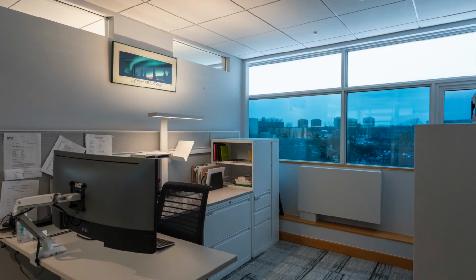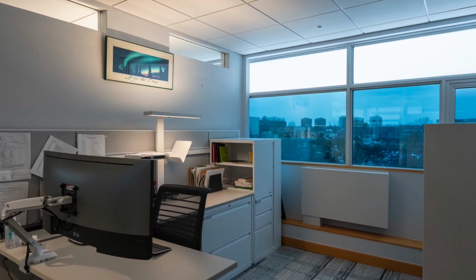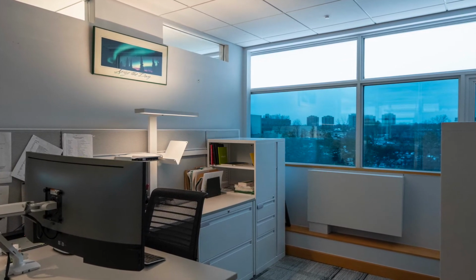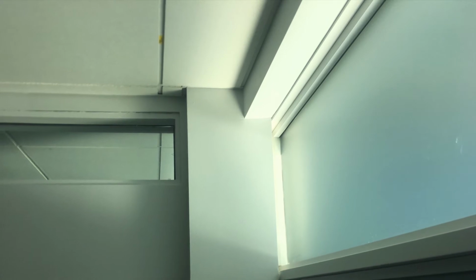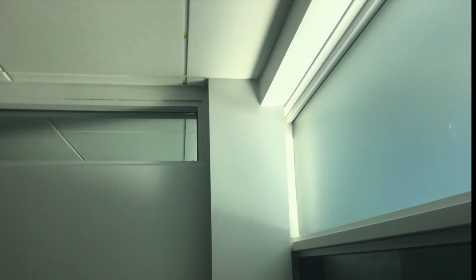Exposed to direct sunlight on south, east, and west facades, the building had ample daylight, but areas were plagued by glare and heat gain. Extensive daylight modeling informed glare-mitigating glazing decisions and lower target illuminances. Daylight redirecting film guides sunlight towards the ceiling, increasing illuminance and perceived brightness. Lower thermochromic windows darken to shield occupants from the sun's glare.